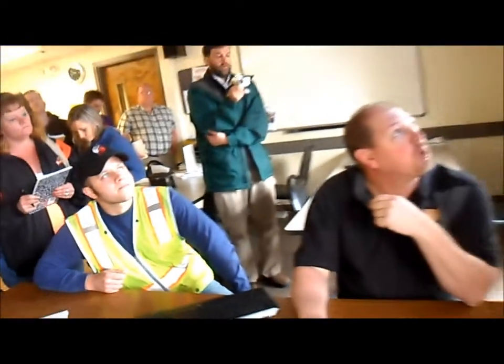And there are some areas even outside of the regulated areas, down in this little purple area right here. Most of the houses in there have about 120 psi, which is really pushing the limit. But at the time when that was installed, there weren't any standards for that. Now, everything has to be 80 or less. So at that time when we supplied water, that was good. We still have a lot of individual home pressure regulators that we put in now. When they start having issues, we install ones on the services instead of just a whole main line.